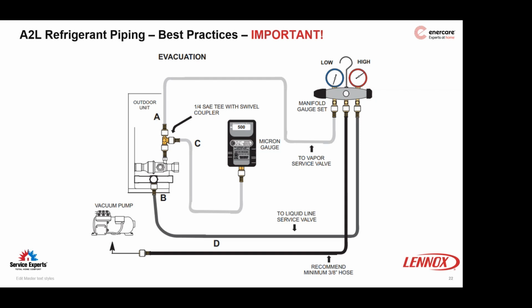Vacuum the system down to at or below 500 microns. Then isolate the system from the vacuum pump for 10 minutes while that micron gauge is still reading. If the micron gauge reading does not exceed 1,000 microns, the evacuation is complete. You can proceed with charging and commissioning.